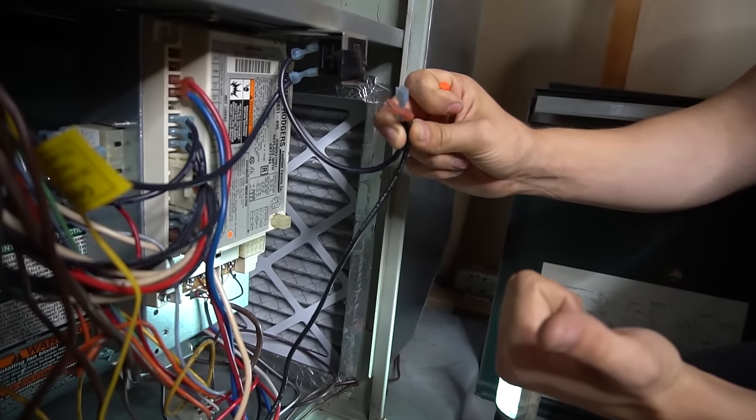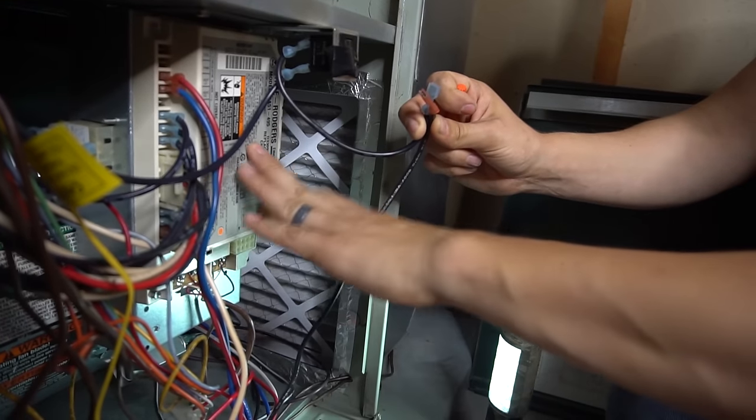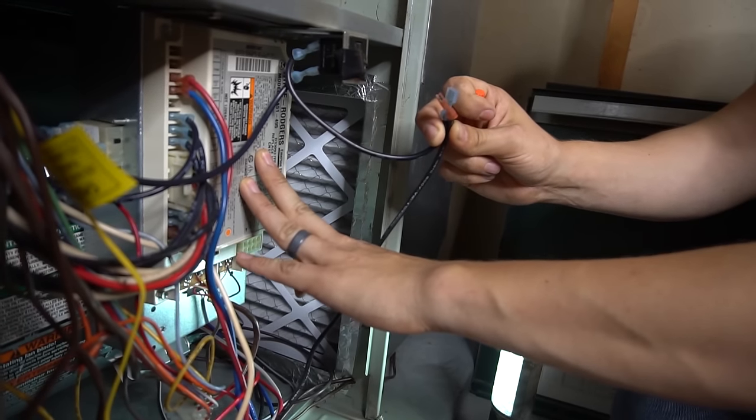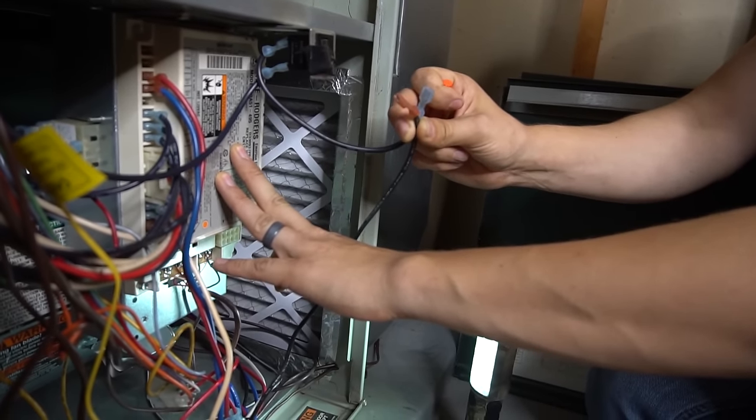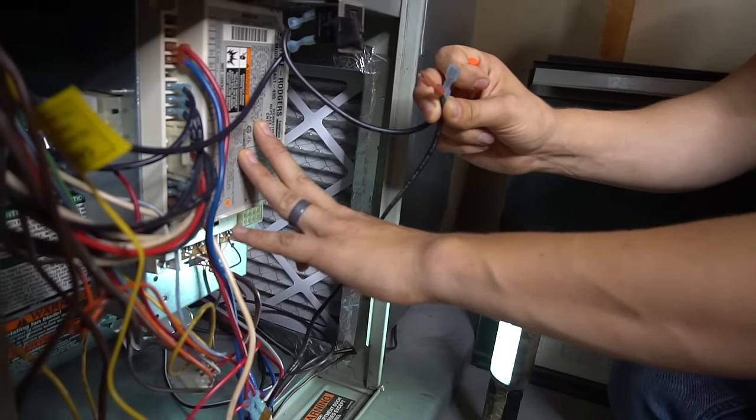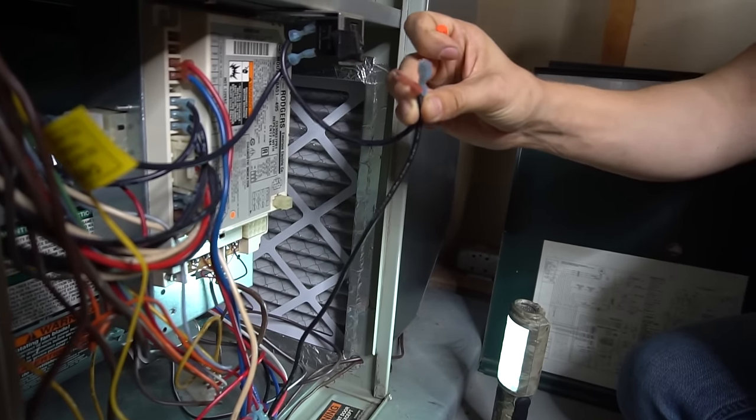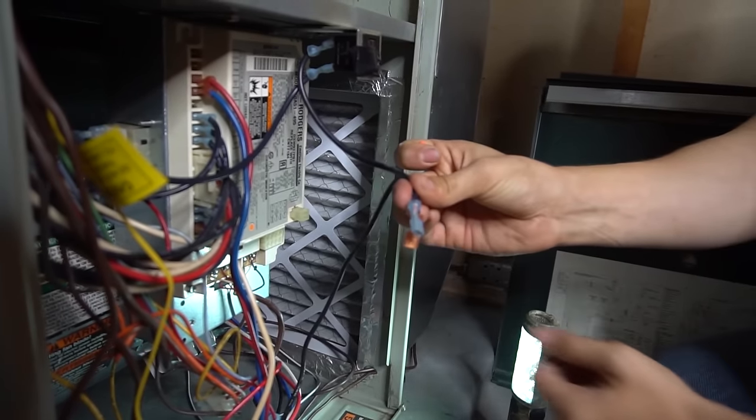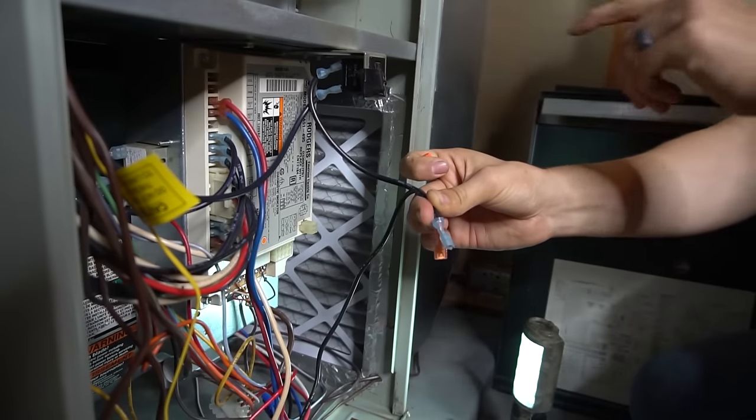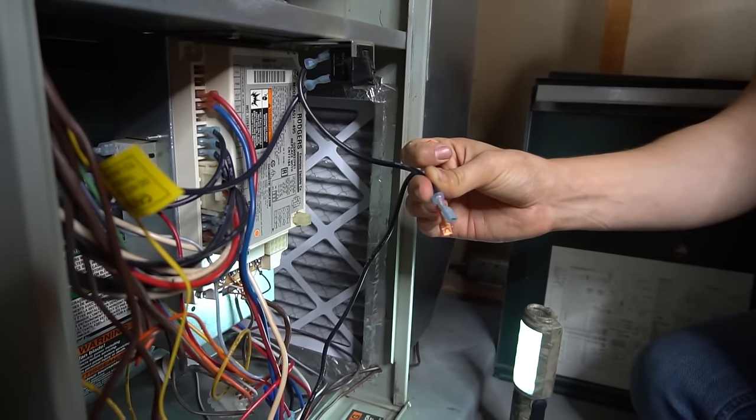If your blower motor comes on, that means you know your control board is bad. It's just not sending power to the motor. If the blower motor does not come on while it's bypassed like that, that means your blower motor is bad and it needs to be replaced.